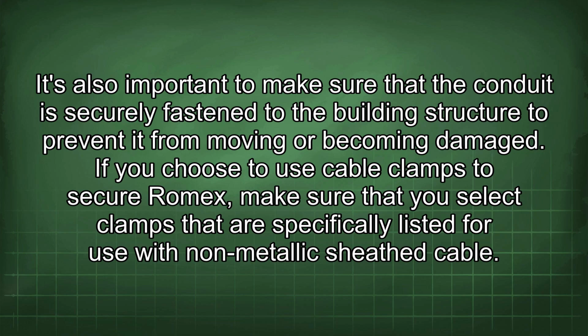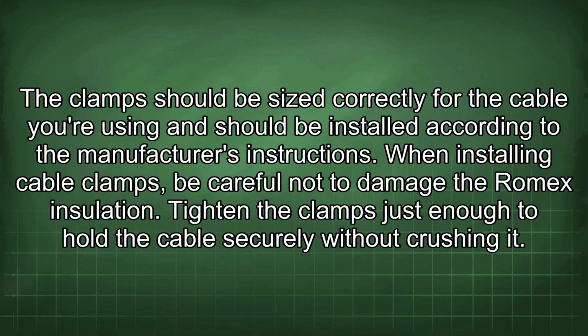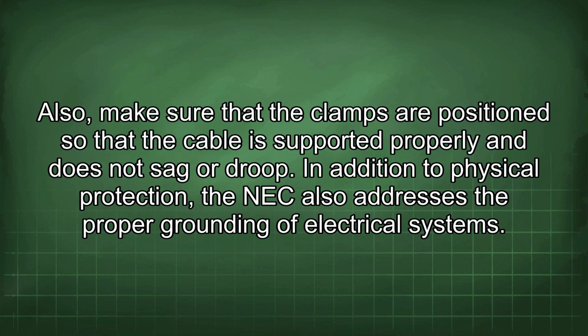If you choose to use cable clamps to secure Romex, make sure that you select clamps that are specifically listed for use with non-metallic sheathed cable. The clamps should be sized correctly for the cable you're using and should be installed according to the manufacturer's instructions. When installing cable clamps, be careful not to damage the Romex insulation. Tighten the clamps just enough to hold the cable securely without crushing it. Also, make sure that the clamps are positioned so that the cable is supported properly and does not sag or droop.